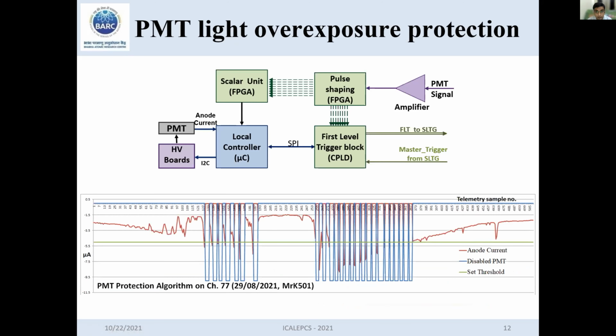Similarly, a PMT light overexposure protection algorithm has been implemented in the local microcontroller, which checks anode currents. For this example, the anode current threshold value is 5 microampere. If it goes beyond that, it switches off the HV supply to that PMT so that the productive life of this PMT can be saved. Once this light interference source goes away, it continues the experiment.